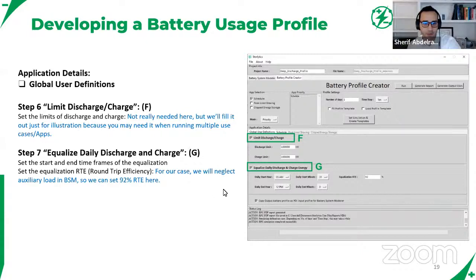Yeah, and I'll just expand on that a bit. When we were preparing for this workshop, among the three of us, we discussed that we really want to focus on the battery side of things, right? Auxiliary load for lithium is considerable. With auxiliary load, if you have a 1 cycle a day application, your round trip efficiency would be around 85% or so.